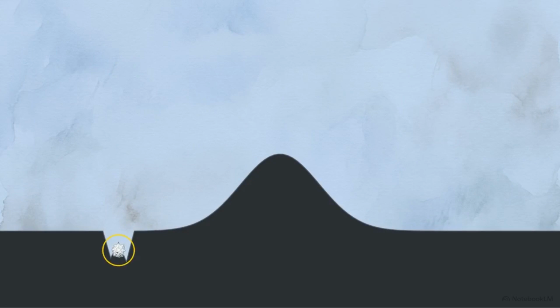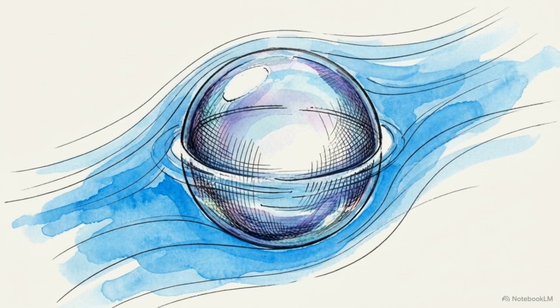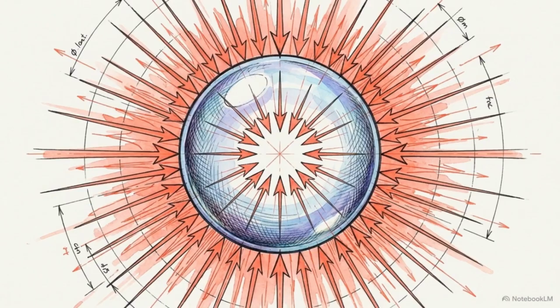This phase failure begins at a cavitation nucleus, a microscopic weakness like a surface scratch where vapor expansion gains a foothold. As flow carries this nucleus into lower pressure zones, the cavity balloons outward, forming a spherical bubble riding along the metal surface. The bubble itself is just harmless vapor. It is merely the temporary geometry that sets the stage for a violent mechanical correction.